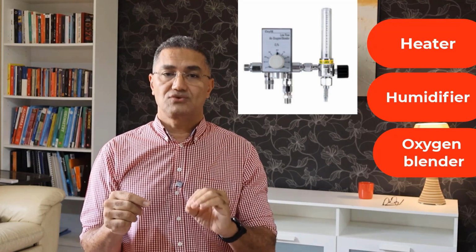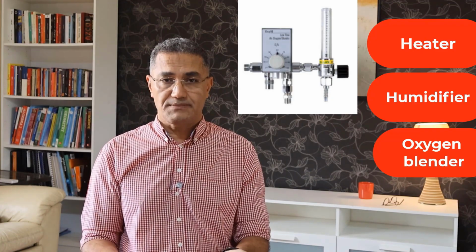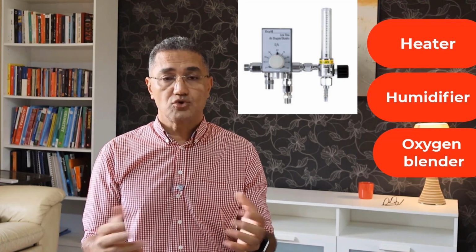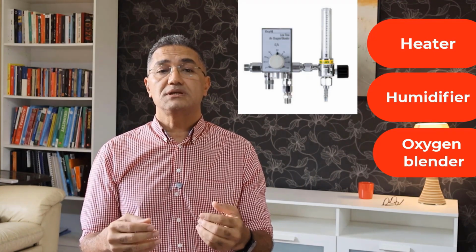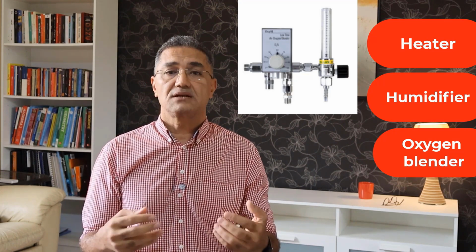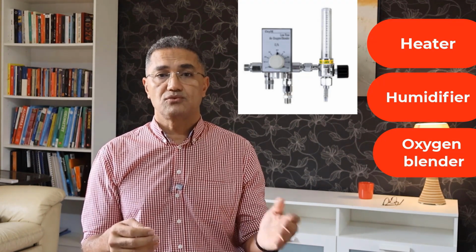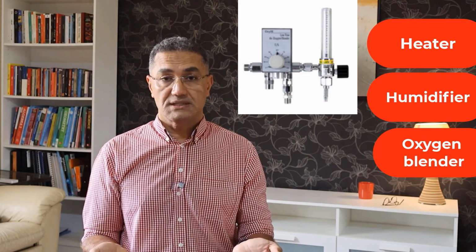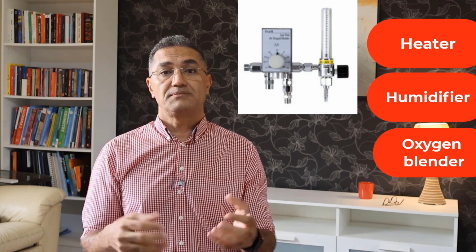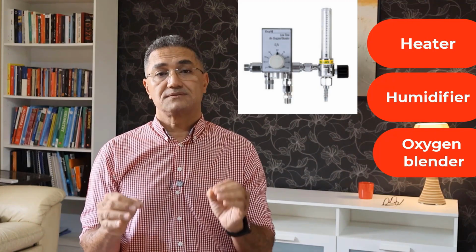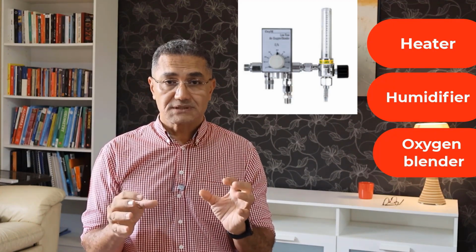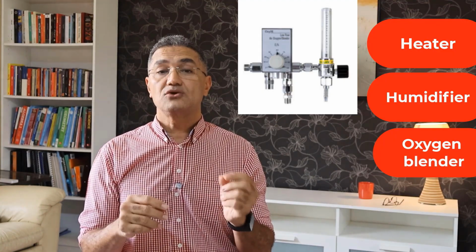What is target saturation? It is the saturation level you want to achieve for the patient. In general, if we talk about the normal range for everyone, it is from 90 to 95, but there are other individuals. Their target saturation might be lower than this, such as in congenital heart disease. It could be above 80 or above 75, so you can't just add more oxygen. Or in some cases, for example, in patients with PPHN, you need to add more oxygen because this helps. So whatever target saturation you want for the patient is related to the FiO2, and you can increase or decrease it through the oxygen. These three are the most important things that must be present in any machine. Any machine should have these three.